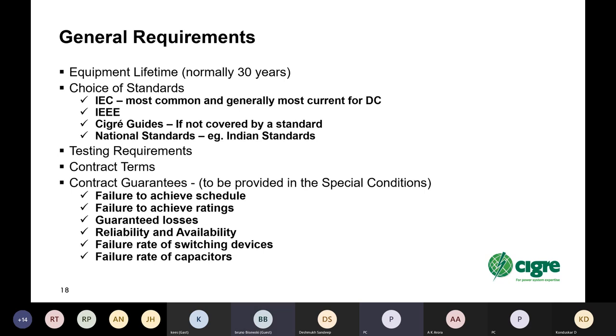Looking at then the specification of the DC equipment, general requirements, equipment lifetime is normally 30 years. Some people use 40 years, and DC systems, for the most part, much of the power equipment can last for up to 40 years. Some of it, of course, will fail and needs to be replaced, but 30 to 40 years is common. Then there's a choice of standards: IEC, IEEE, CIGRE guides, and national standards. IEC is the most common and generally most up-to-date or current for DC systems.